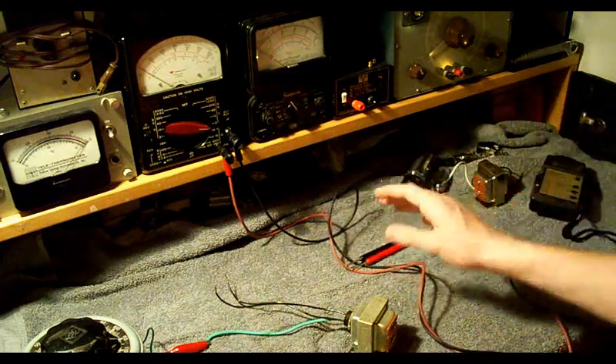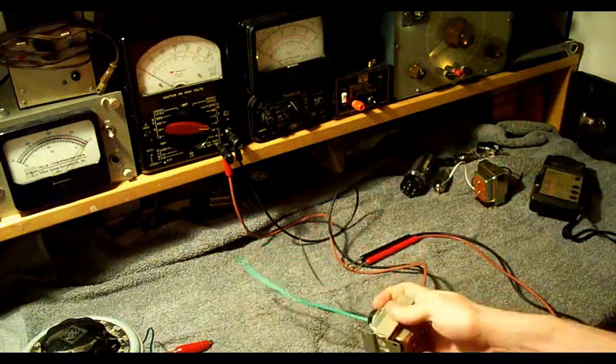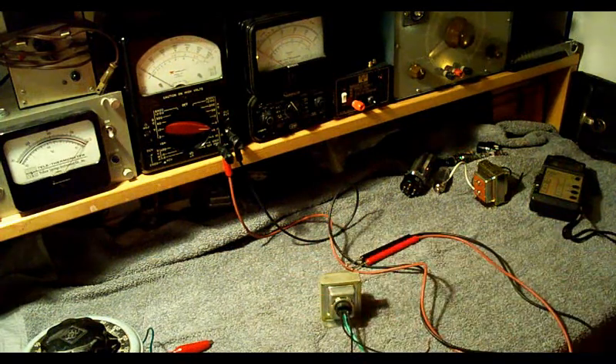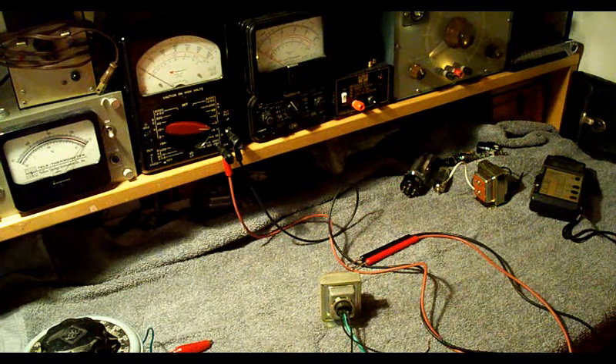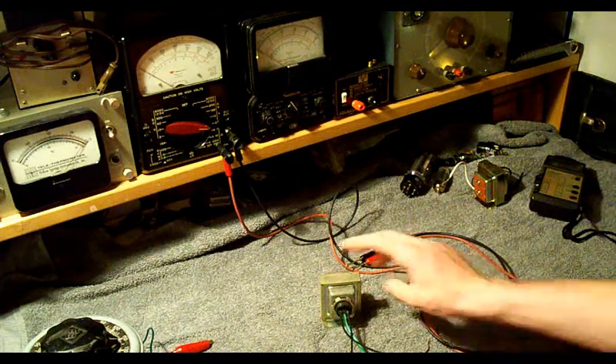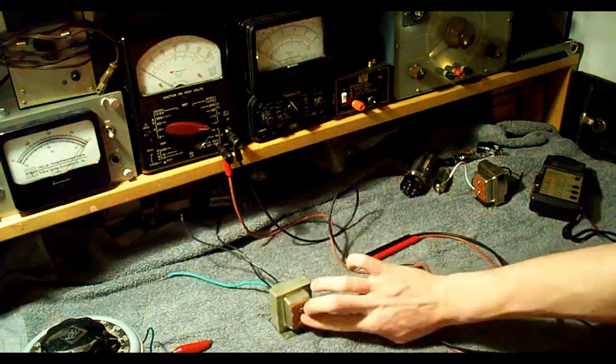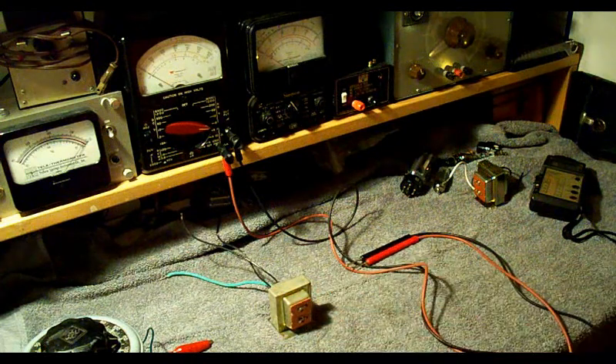And the scary thing about this is, if I hook this up to power, it won't trip a breaker and it won't cause any problems. I hooked this up and I measured the output voltage, and I expected to get anywhere from 10 to 15 volts depending on the input voltage. And I got full line voltage coming out of these screw terminals. And it didn't trip a breaker. And that is why you always want to check something like this.